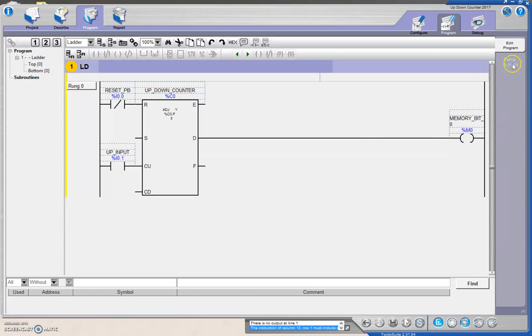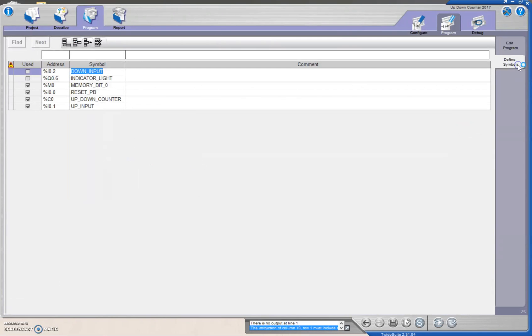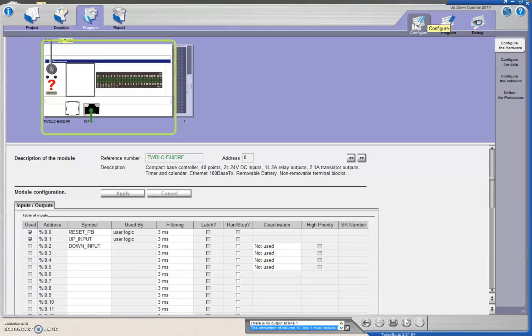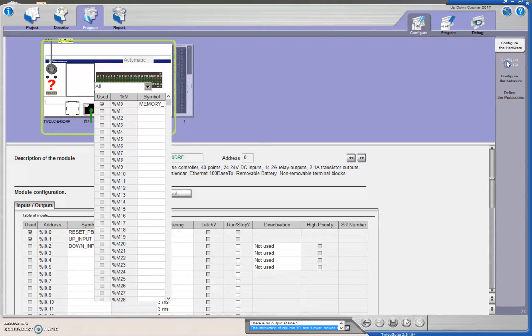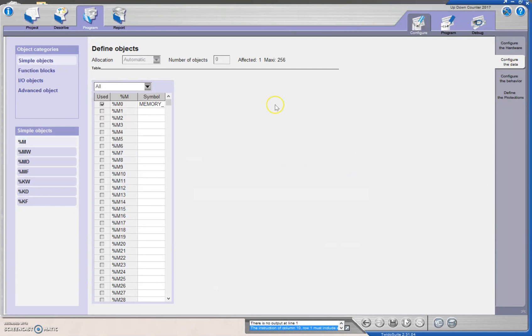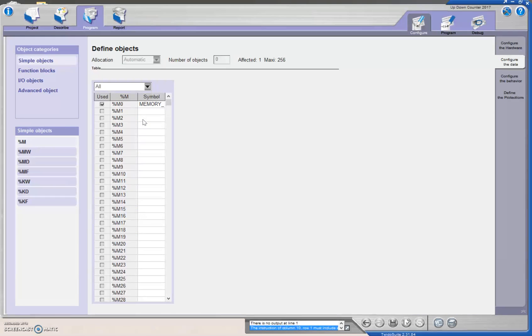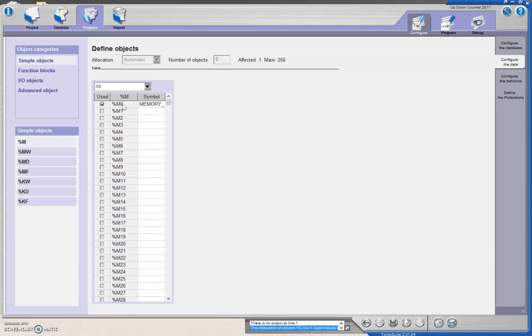If I go to define symbols, then you can see that I've defined it right here. Where I've done that, is I've gone into configure, and I've gone to configure the data. It's not actually a piece of hardware, it's just a soft relay, and there are my memory bits. So I have all these different bits that I can use as internal relays. If you just want to control something else later on the program, you can make use of these memory bits rather than actually wiring up a relay.